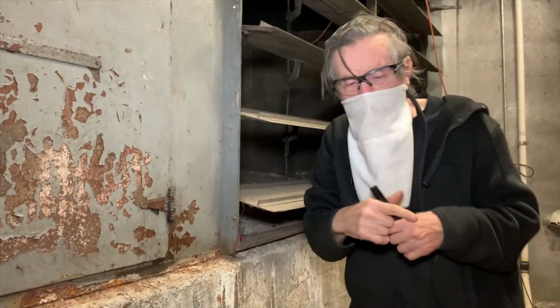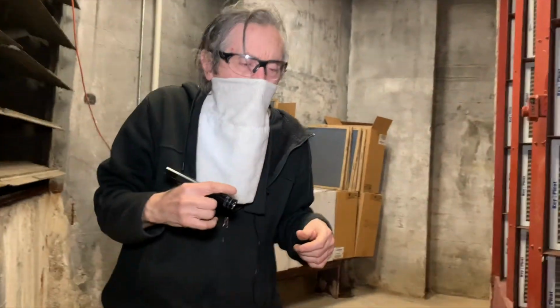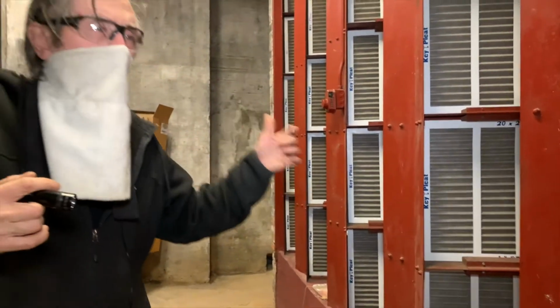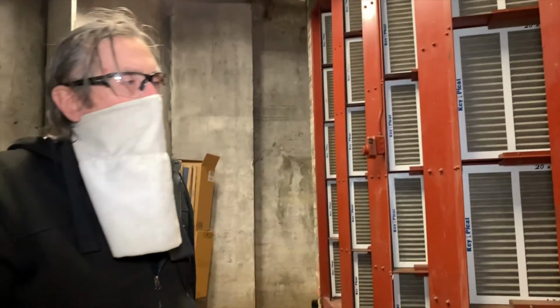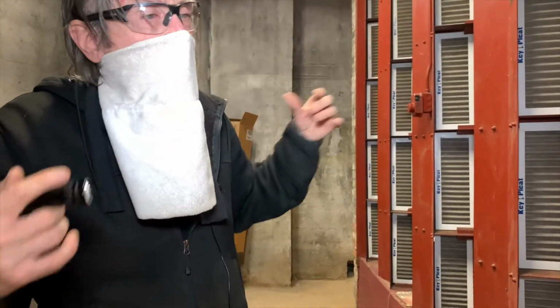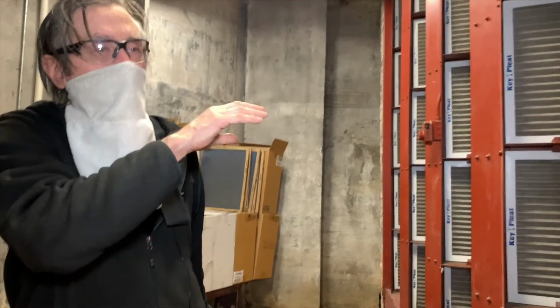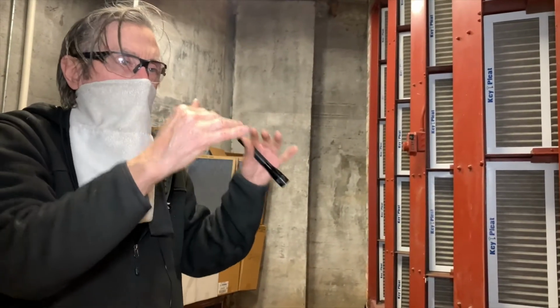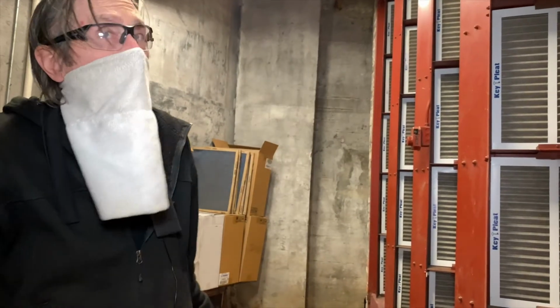And of course, all that works in the opposite way when we are cooling. We take water out of a well that we have over here, and we pump it through the heat exchangers, and it's all working in reverse. The overheated air that is too hot for the people blows through the heat exchangers, and that cold water inside of those heat exchangers pulls the temperature down.